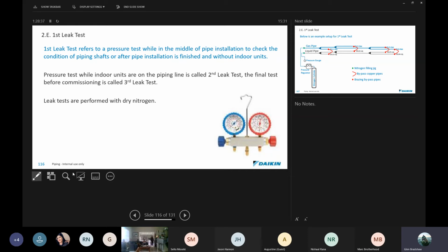If you skipped leak test 1 and 2 and only did leak test 3, you might end up looking at a number of floors of piping, which is going to make finding a very small leak very difficult. Whereas if you pressure test your piping at the end of every day, then the next morning you'll very quickly be able to ascertain whether you actually have a leak or not. So it's very important. What I have seen guys do is, when they've completed installation and know they're not going to be commissioning for some time, they put the system under pressure so that when they come back they're able to see, and you're getting a pressure test over a much longer period of time.